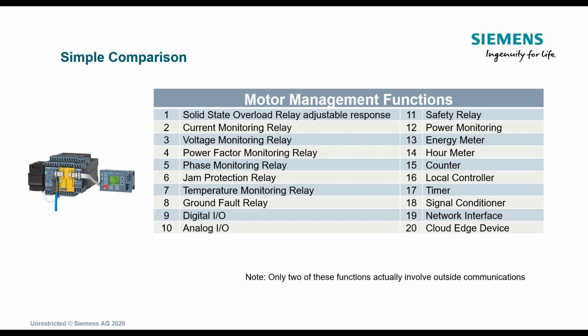You can see that, hey, mechanically, maybe these bearings are getting some friction and heating up, or maybe I'm getting a vibration and I need to bring in a vibration sensor, and if this vibration gets up to a certain amount of G's, please trip the motor, because now we're maybe badly misaligned or something else mechanically has gone wrong. So I can go up to 6 RTDs into SIMOCODE. Ground fault relay, I can add additional digital inputs for different scenarios of interlocks or bypass or permissives.